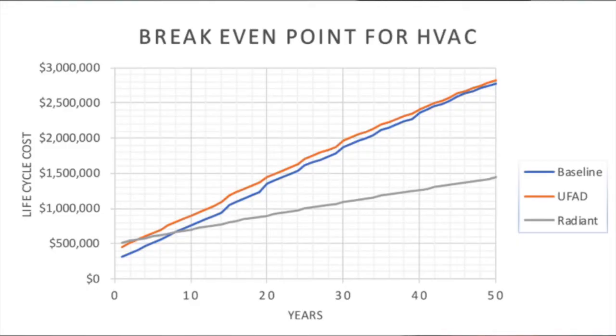Simulations that were done in IESVE Pro to compare the two alternative options against the 90.1 baseline proved that the Radiant Floor/DOAS system saved about 30% from the baseline. Considering it with the high performance envelope, energy consumption is reduced by 59%. With this amount of energy being saved, the owner will break even on their additional investment after only 8 years and will save $1.4 million over the building's 50-year lifespan.